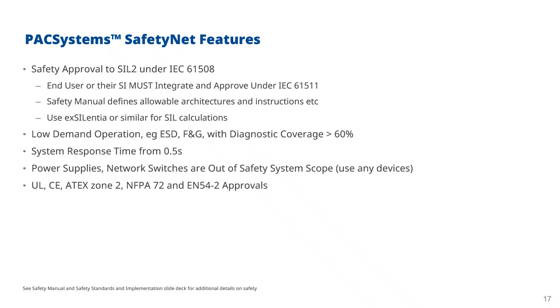And why is that needed? Well, if anything does go catastrophically wrong, someone is probably going to review what happened. In the UK, that would be the Health and Safety Executive or the HSE, and they would want proof that you performed due diligence and that you made the system as safe as you reasonably could, and that you operated the system in a safe manner. And those calculations are part of that documentation to prove that you did as much as you can to mitigate any safety issues.